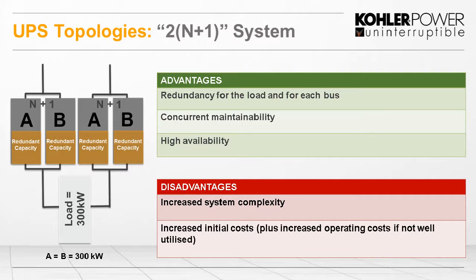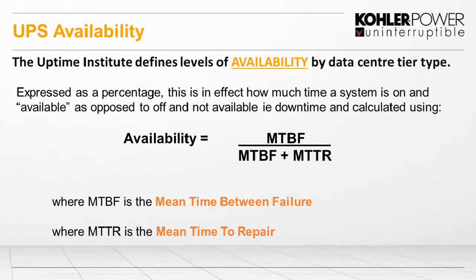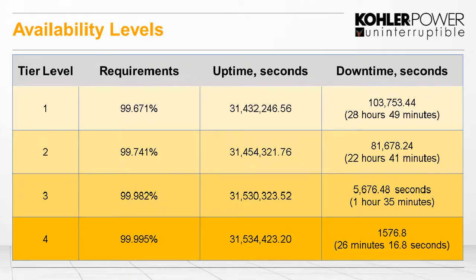So the actual availability, what is that? Now, the Uptime Institute defines levels of availability for the data center tiers, and they calculate availability as MTBF over MTBF plus MTTR. That is the mean time between failure and the mean time to repair. So we look at the levels in a data center, and you see a tier 1 level here has a requirement to be 99.671% available, rising to tier 4 of 99.995% availability.